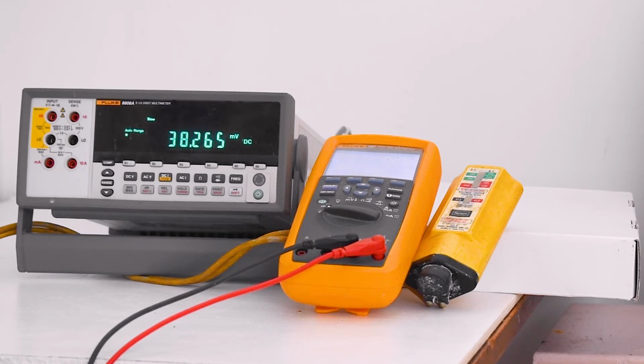The wiggy should not be connected to a sensitive circuit or remain connected to house current for more than a few seconds, as the meter itself can be overloaded and damaged. Many applications lend themselves to the solenoid voltmeter. For example, to test a GFCI, connect the wiggy probes to the hot wire, black, and grounding conductor, green or bare. The high impedance meter does not draw enough current, 4 to 6 milliamps, to trip the GFCI.